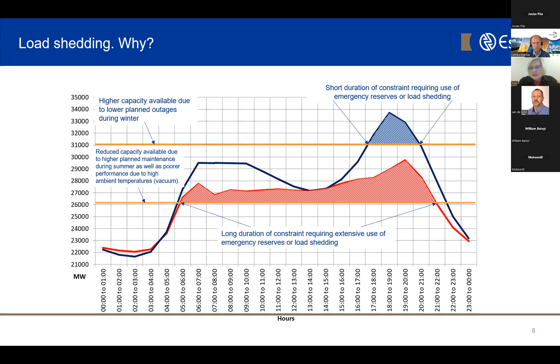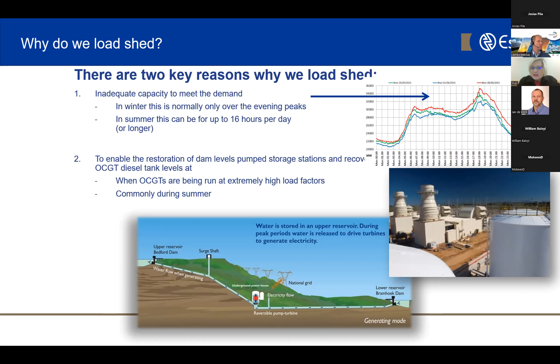So essentially, why do we load shed? We load shed to manage capacity and demand, as explained with the peaks. The other reason is we need to replenish our emergency supplies. At all times we keep an emergency reserve of 2,200 megawatts on the network, to cater for any quick events so we can keep the network stable. Typically this involves our pump storage stations and our gas OCGT stations, pictured here.